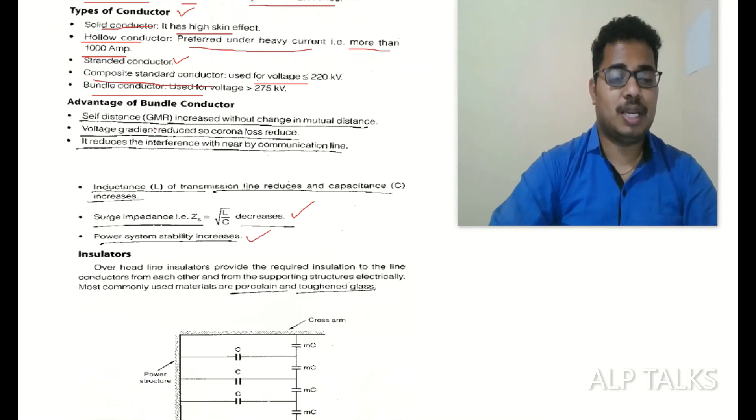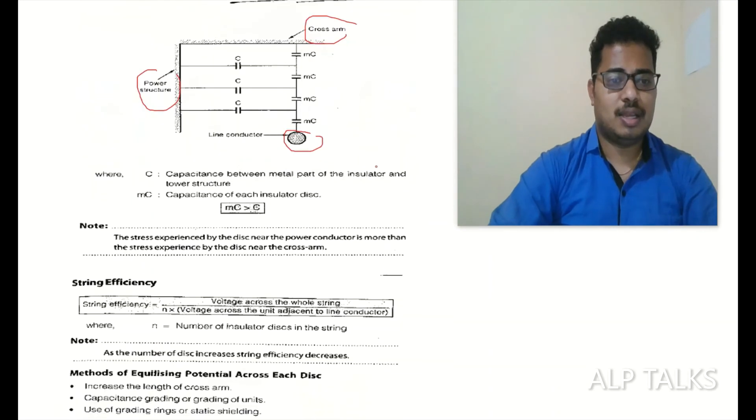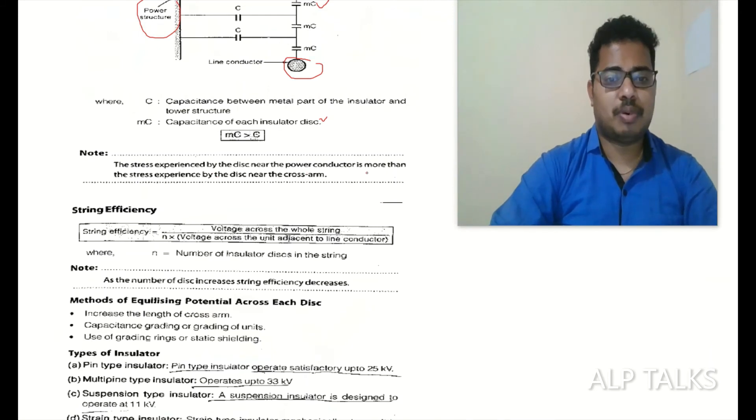It's better to go for bundle conductor. Insulators: we will use just to isolate the conductor from power structure and cross arm power lines. Insulators provide the required insulation to the line conductor from each other and from supporting structure electrically. Most commonly used materials are porcelain and toughened glass. The capacitance C: capacitance between metal part of the insulator and tower structure. MC: capacitance of each insulator disc.